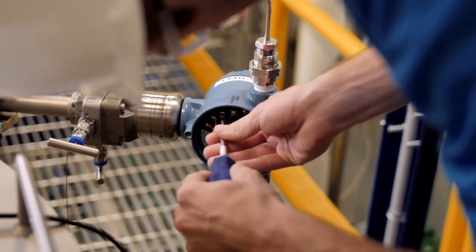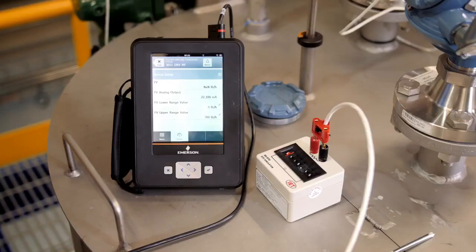We will start by first removing the RTD leads from the transmitter and connecting the simulators. Once again, go to the calibration page of the Trex and select the process temperature trim option.